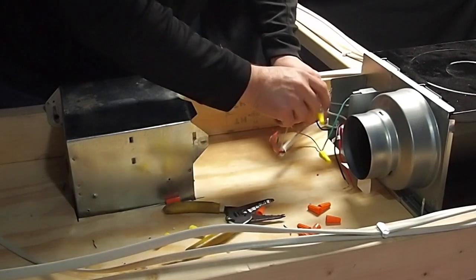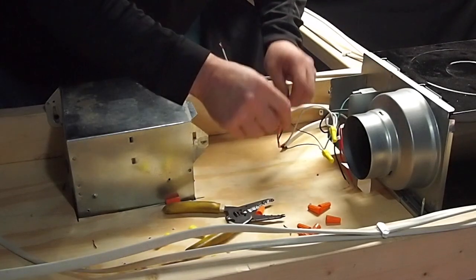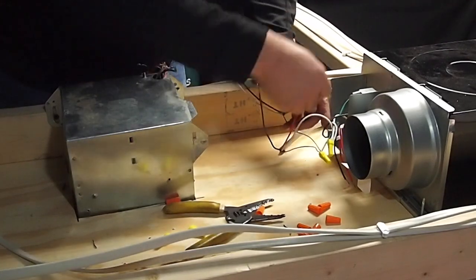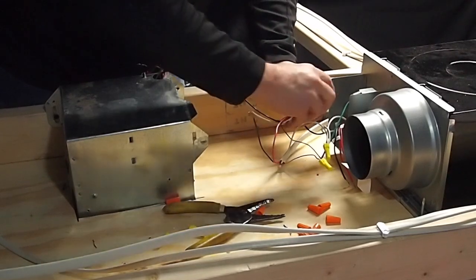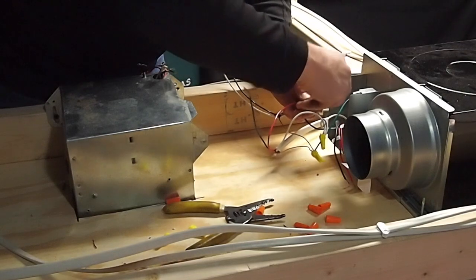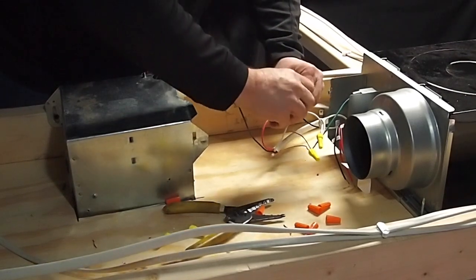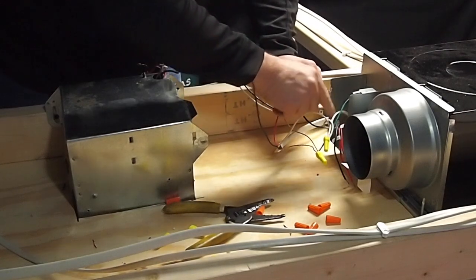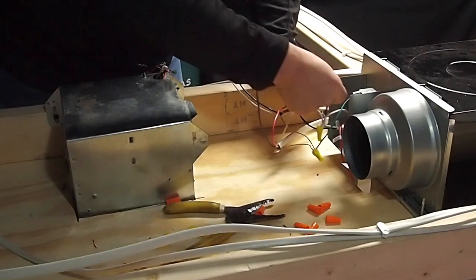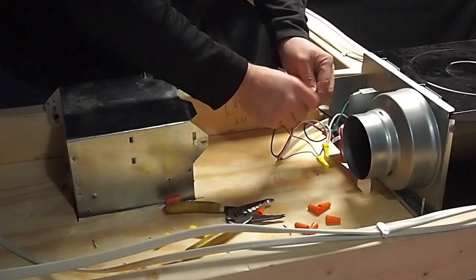We are going to have that done. Now we are going to hook up the wire for the white. If you can remember down at the switches we use the red to switch the light on and off. We are going to get that hooked up. Now the black wire which has constant power to it, we are going to put it straight to the fan.